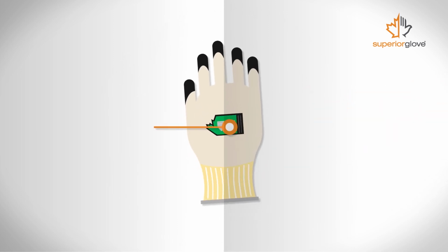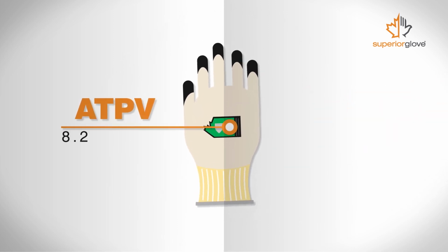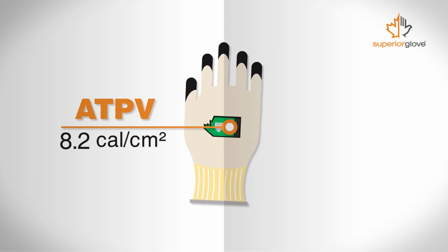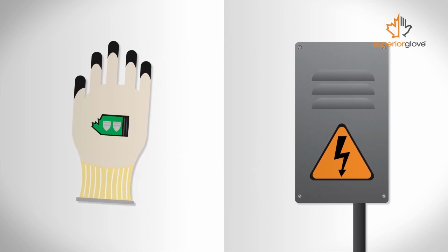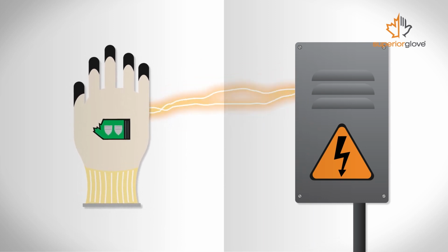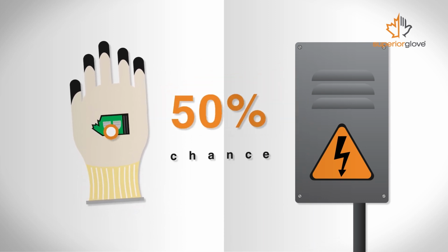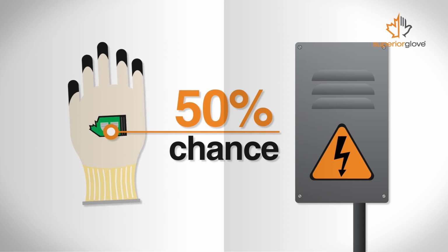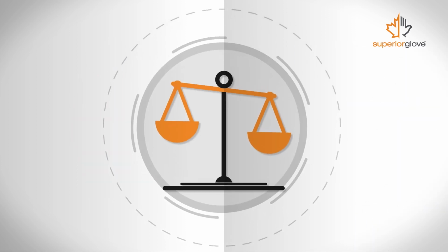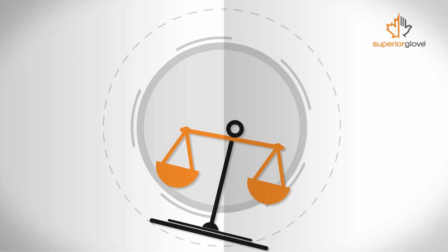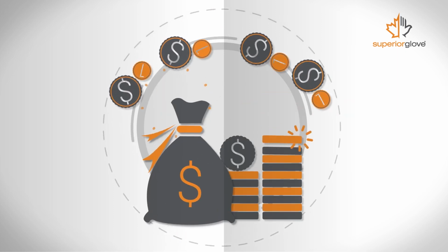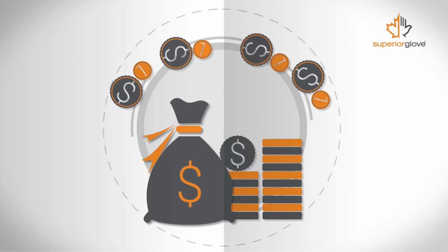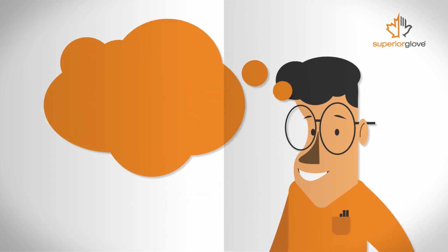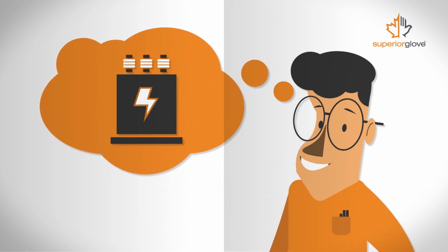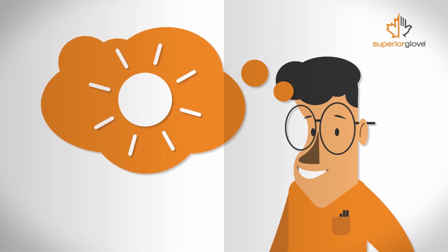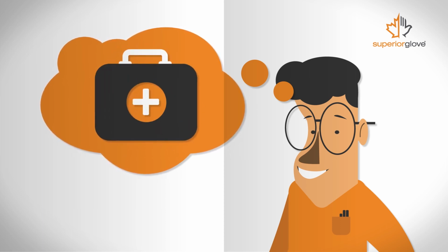So let's say you have a glove with an ATPV of 8.2 calories per centimeter squared. That means if the arc flash's incident energy is 8.2 calories per centimeter squared, you have a 50% chance of getting a second-degree burn. Those odds might not sound great, but imagine if you were given a 50% chance of winning the lottery. Suddenly, those odds sound pretty good. And think about it. Escaping an electrical explosion that is 4 times hotter than the sun with only second-degree burns is a bit like winning the lottery.